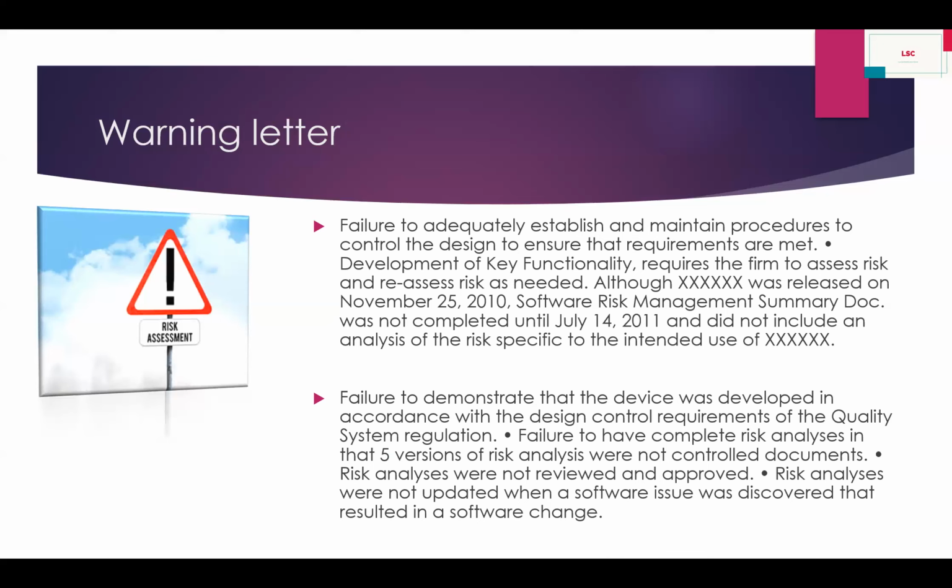Failure to demonstrate that the device was developed in accordance with the design control requirements of the quality system regulation. Failure to have a complete risk analysis: five versions of the risk analysis were not controlled documents.